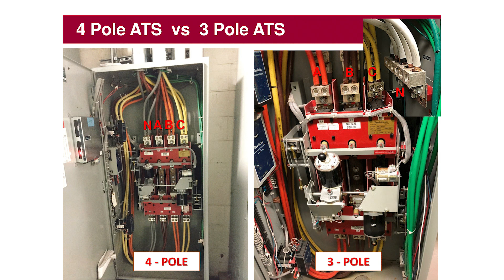Remember, a transfer switch is just switching. It's a big switch, and it's just switching the A, B, and C phases. These are 3-phase power systems, so it's just switching your phase conductors. Your neutral conductor is over here, it is not switched. The neutrals from the normal, the emergency, and the load all come together on a common set of lugs. That's why it's called a 3-pole switch, we're only switching 1, 2, 3 poles.